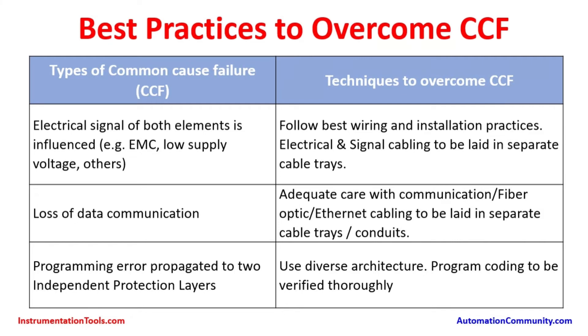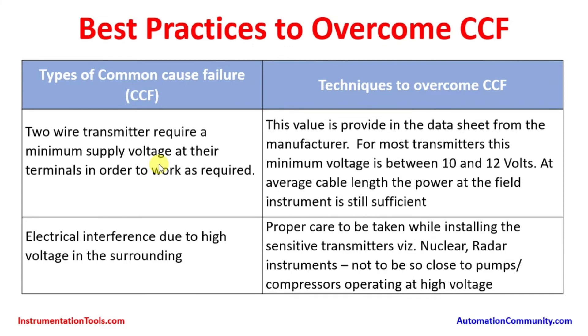If there is a programming error in the logic solver application program, it may impact the actual logic to be performed. It is ideal to have two different types of processors for the basic process control system and the safety instrumented system. As far as possible, use diverse technology and diverse architecture. The application program must be verified thoroughly.